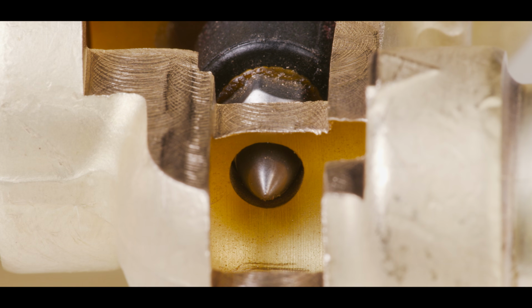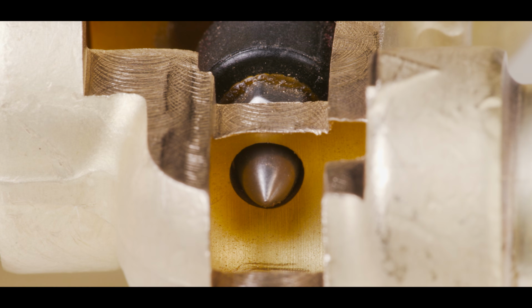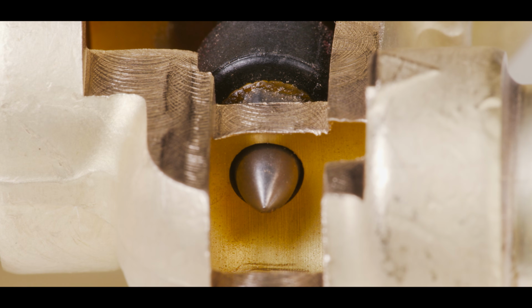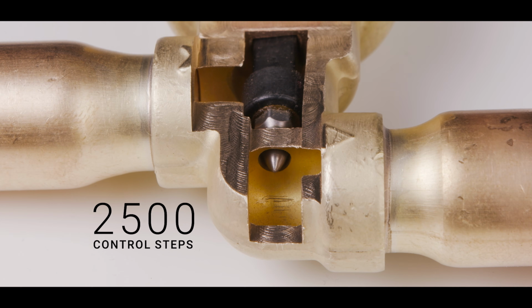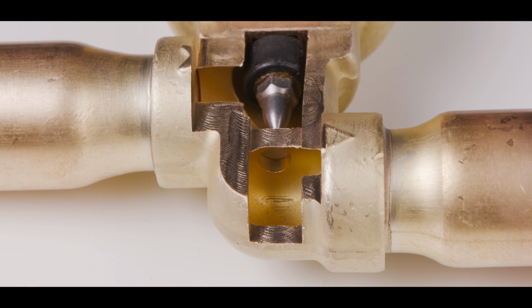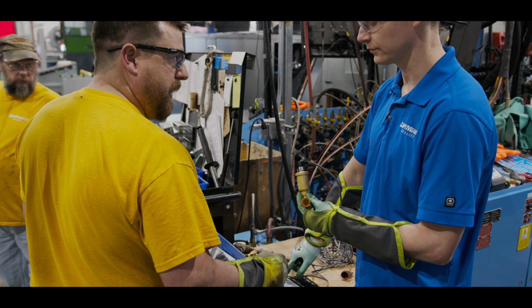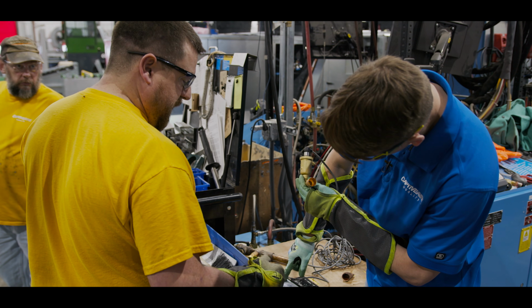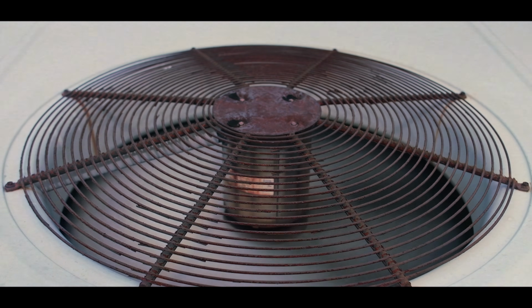So how accurate can we be? Well, in this valve, we have 2,500 steps of control between the needle being completely closed and completely open. So we can be extremely precise on how we meter refrigerant. Using these valves was one thing we got right from the get-go, but we weren't always so lucky.